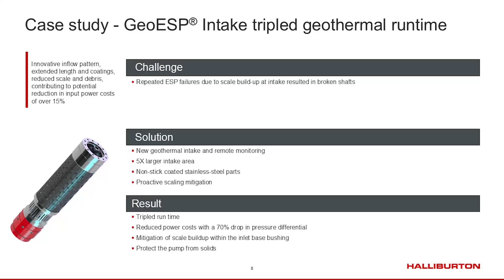So ultimately, the result is we tripled runtime. The latest system is still running at 3+ years, so we're still doing good on that. The nice part is we reduced power costs at the same time. Allowing that larger intake area and smaller pressure drop meant the pump didn't have to work as hard. So we reduced power costs, actually 15% in this well. So it was a huge, huge difference.